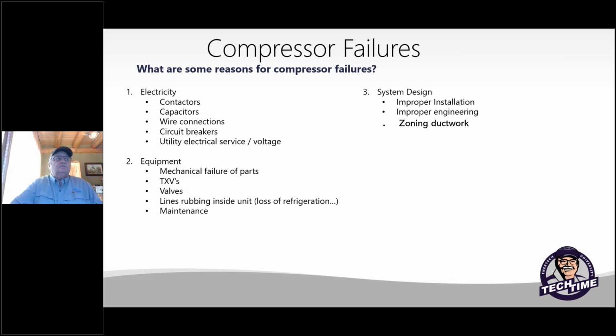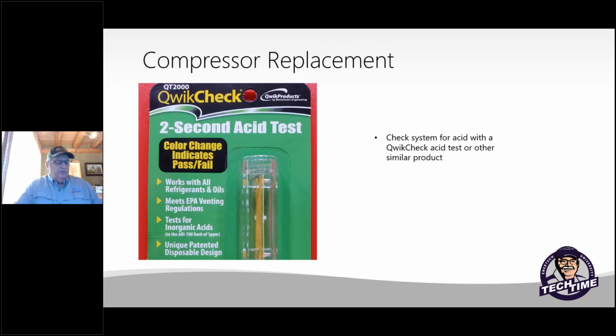So if you do have a compressor that's burnt out or bad, I should say, I always recommend checking with some form of an acid test kit to make sure that there's no acid in the system, and how bad it is. This is very useful after the compressor's been changed and ran too, to double check to make sure you got it all cleaned up.